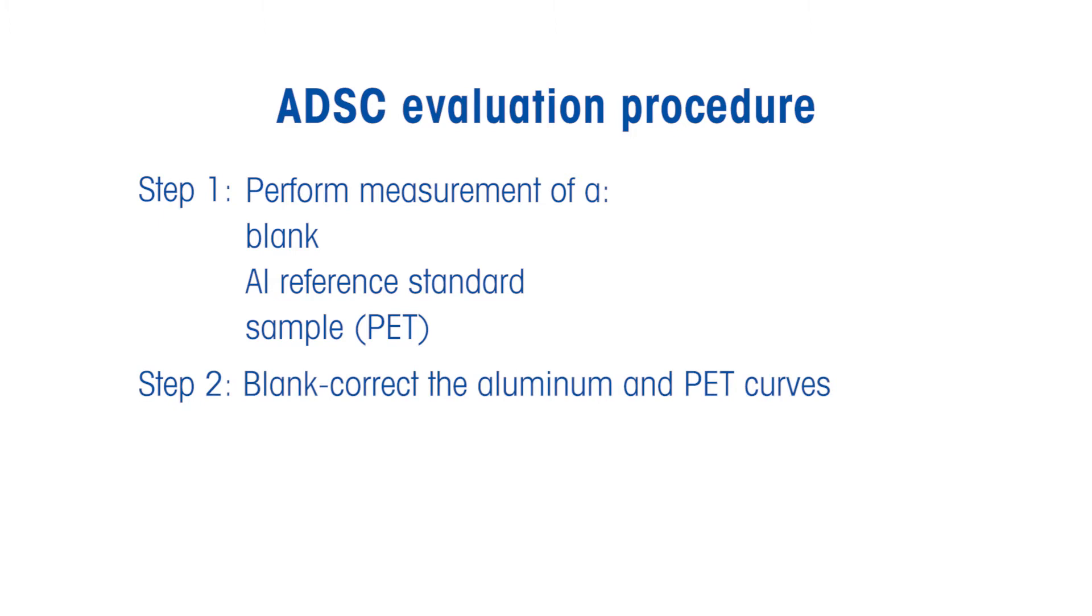Second, blank correct the reference and sample curves. Third, calculate the heat capacity, reversing and non-reversing curves, and phase angle. The phase angle is the delay in the heat flow response to the temperature modulation.